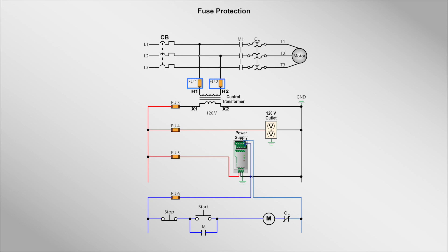These fuses can be placed on the primary, secondary, or on both sides. Here at ISCA, we have made it a good practice to protect both the primary and secondary of the transformer. The fuse or circuit breakers must also be properly sized for the control circuit.